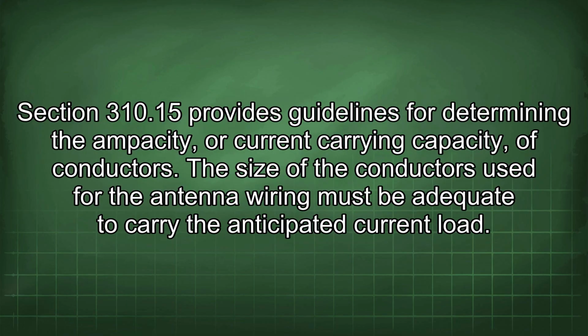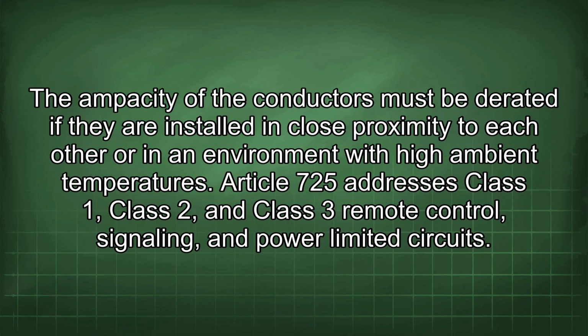Article 310 covers conductors for general wiring. Section 310.15 provides guidelines for determining the ampacity, or current carrying capacity, of conductors. The size of the conductors used for the antenna wiring must be adequate to carry the anticipated current load. The ampacity of the conductors must be derated if they are installed in close proximity to each other or in an environment with high ambient temperatures.